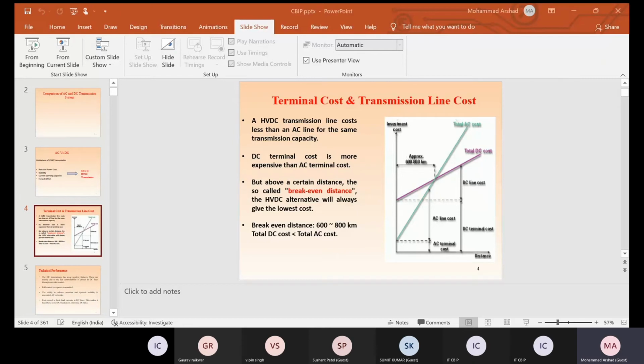Below that intersection point, the AC system cost is well below the DC cost. We call that point the break-even point. Break-even point means if we transmit power below the break-even distance, it is preferable up to that distance. This break-even distance depends on manufacturer to manufacturer, designer to designer, and on the systems. It will vary between 600 to 800 kilometers.